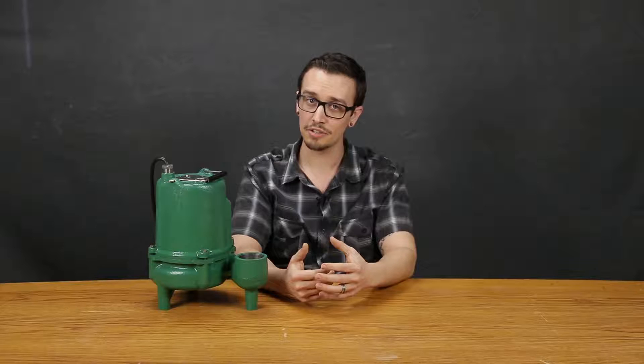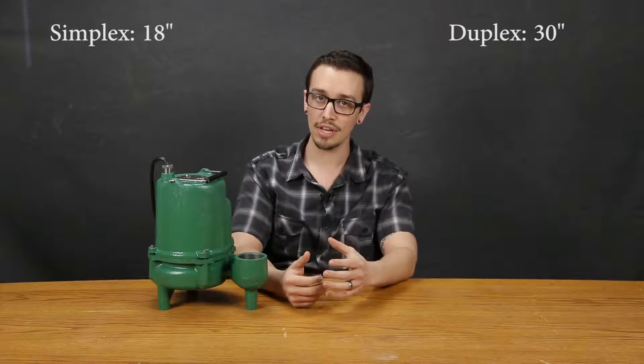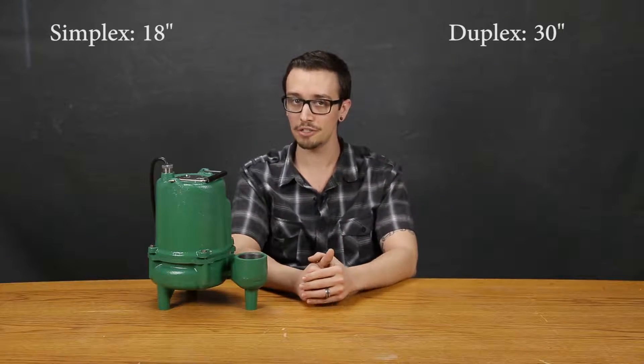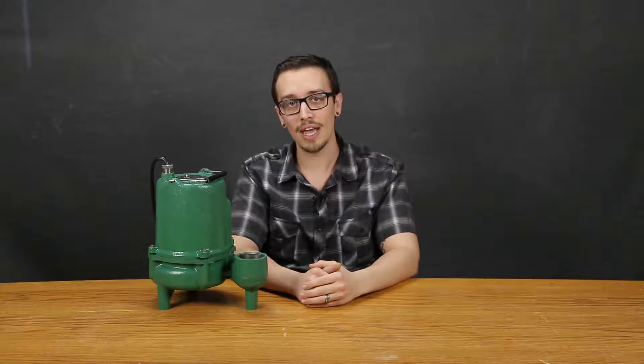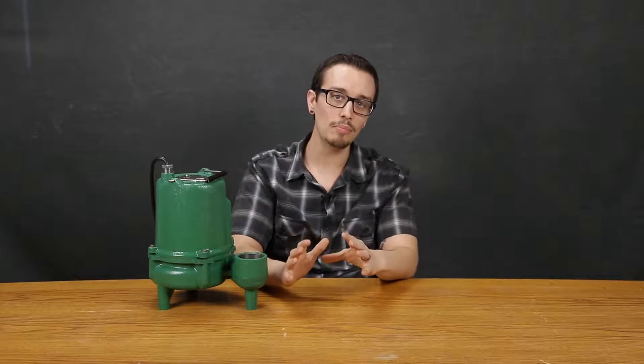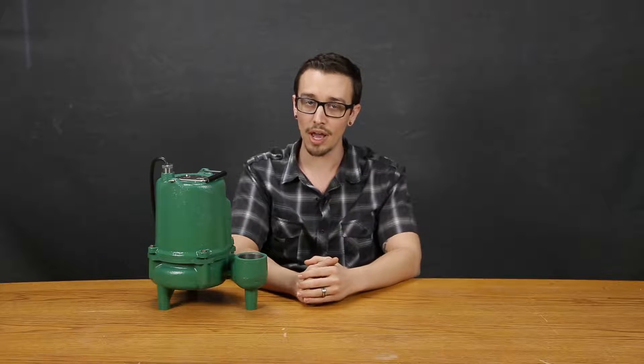The minimum diameter recommended for this pump in a simplex configuration is 18 inches and 30 inches for a duplex configuration. By maintaining this minimal diameter, we are ensuring that the equipment has enough room for proper operation and helps eliminate cord entanglement.